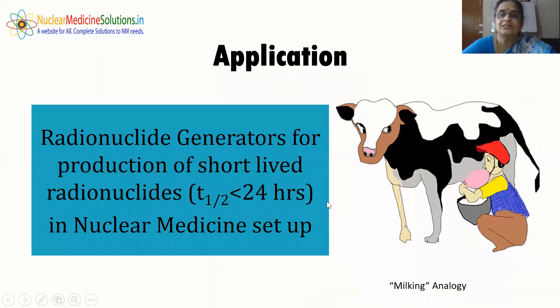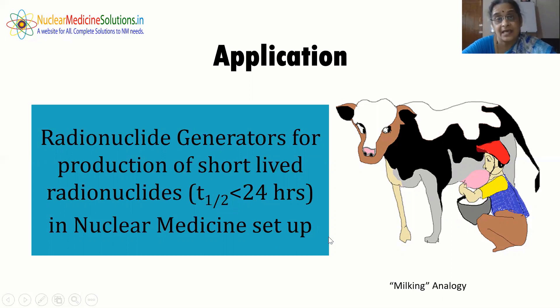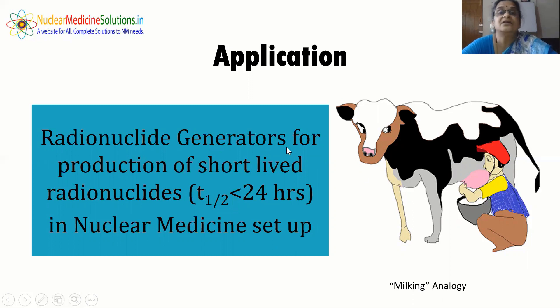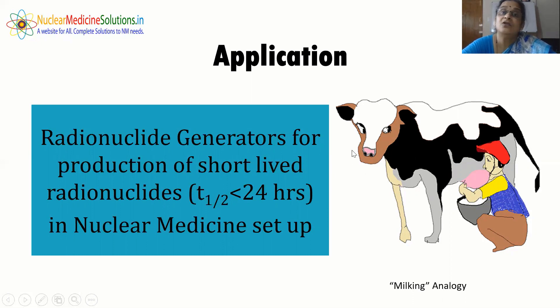The application is about radionuclide generators for the production of short-lived radionuclides with a half-life less than 24 hours — an in-house secondary production mode of radionuclides. These generators are called 'cows.' The most famous cow is the molybdenum-technetium generator, with Tc-99m being the workhorse radionuclide for nuclear medicine imaging and the most used gamma source.